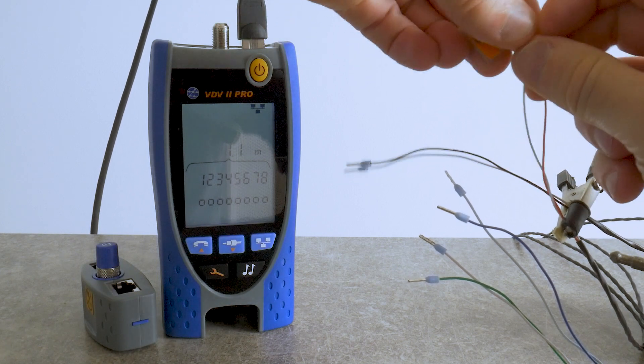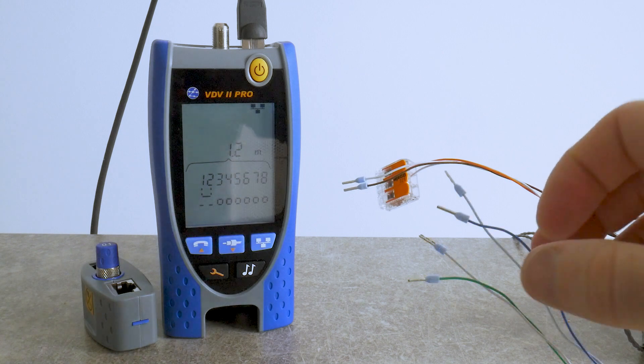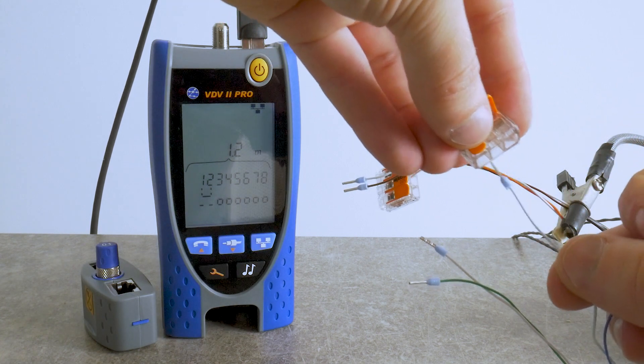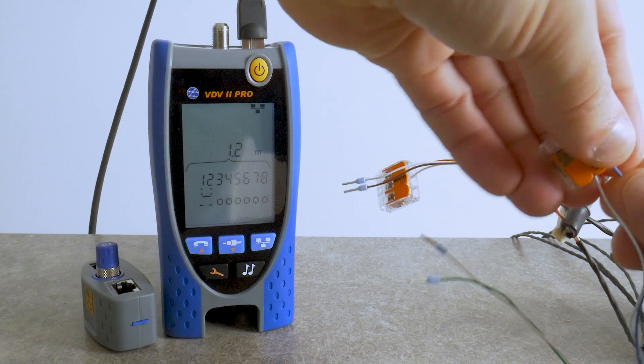Not all TDR meters can do that. Shorting pin 1 to pin 2 — instant result on screen. The graph could be better; at this point we don't use half of the screen, but it still gives what I need, fast.